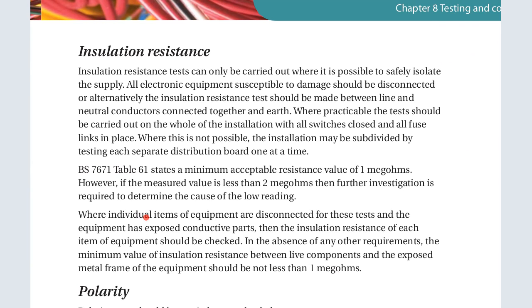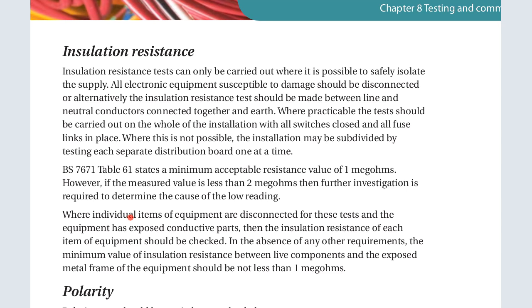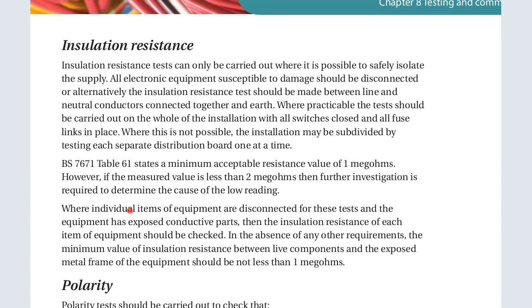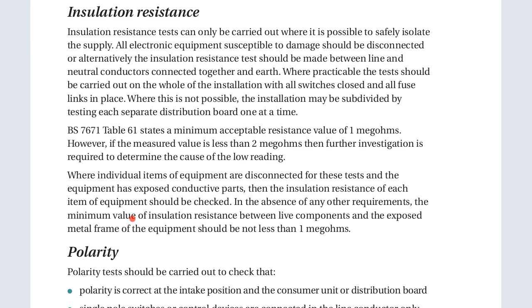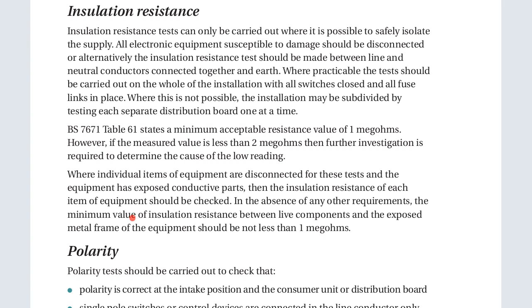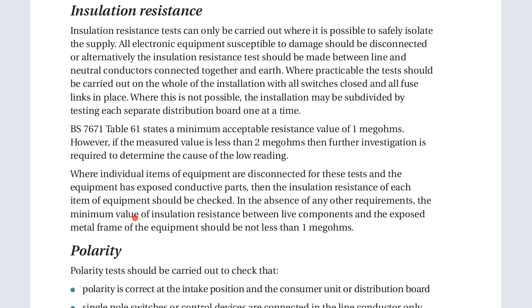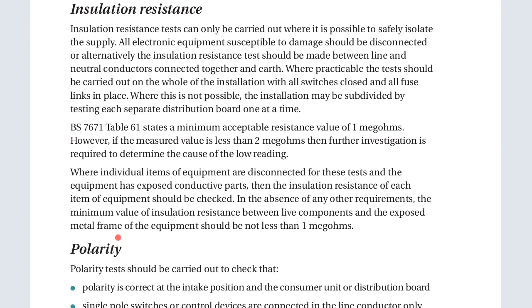So all electronic equipment susceptible to damage should be disconnected, or alternatively, the insulation resistance test should be made between line and neutral conductors connected together and the earth. Where practicable, the test should be carried out on the whole of the installation with all switches closed and all fuse links in place. Where this is not possible, the installation may be subdivided by testing each separate distribution board one at a time.